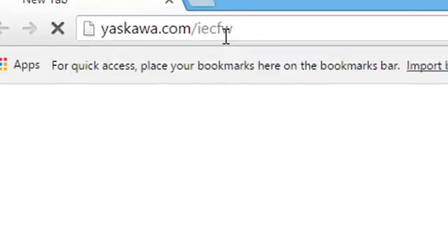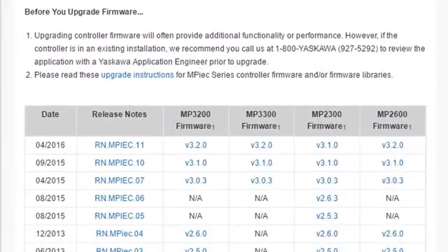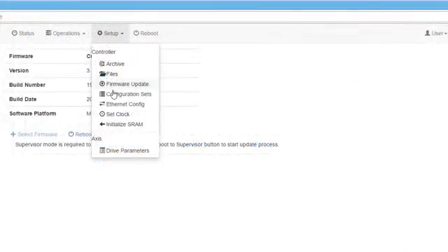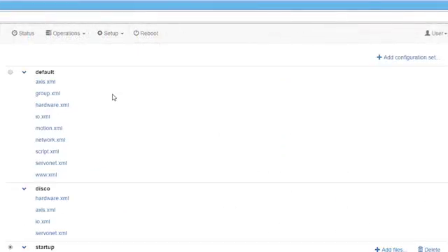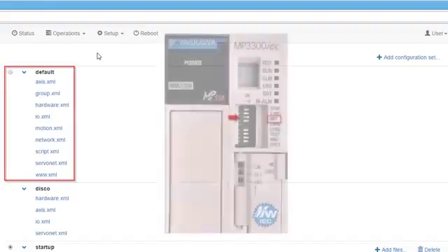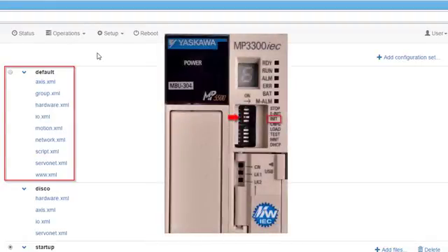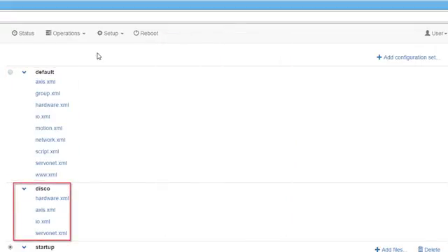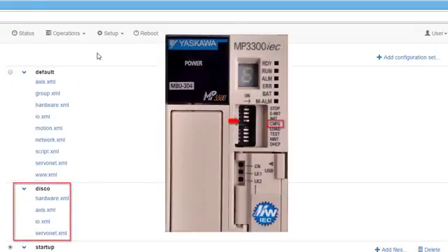The default section is used when the init switch is turned on. This configuration has all of the controller's default settings, and these settings are permanently saved to the controller and cannot be removed. The disco configuration is used when the config switch is set on the controller, and when there is no startup configuration. This configuration updates upon reboot to find new hardware that is attached to the controller. The startup configuration is created when the hardware configuration is saved in MotionWorks IEC. It is not recommended to view or delete the startup configuration files.